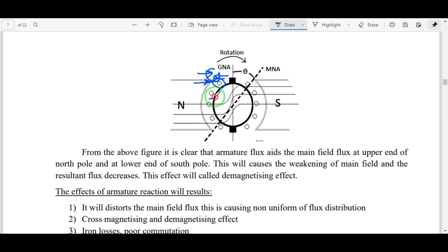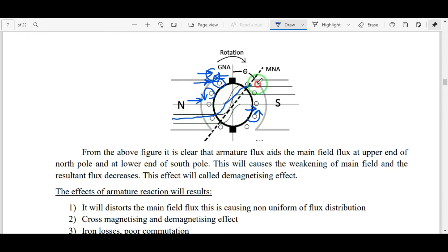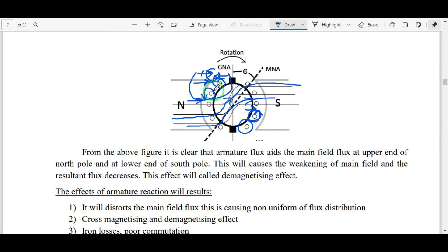Where the armature flux and main field flux are in the same region but crossing, the cross-magnetizing effect causes the resultant magnetic flux to bend. The main field flux lines are distorted — they shift direction from the original north-to-south path. In some regions the flux is strengthened, in others it is weakened, because of the combined cross-magnetizing and de-magnetizing effects.